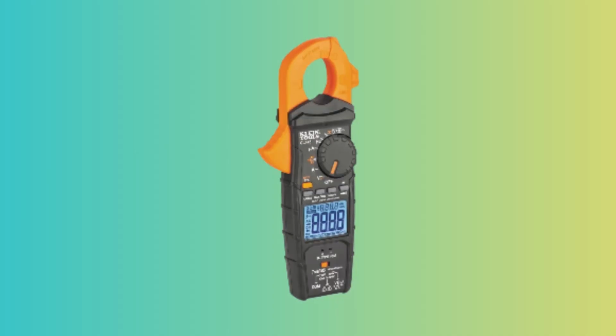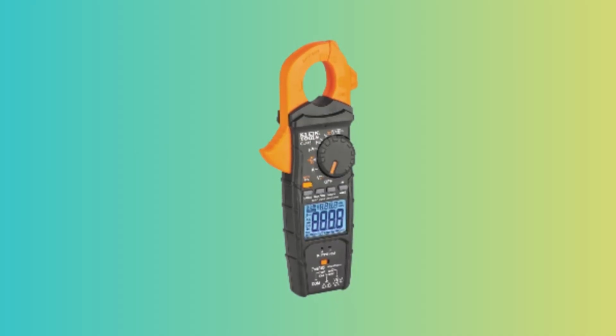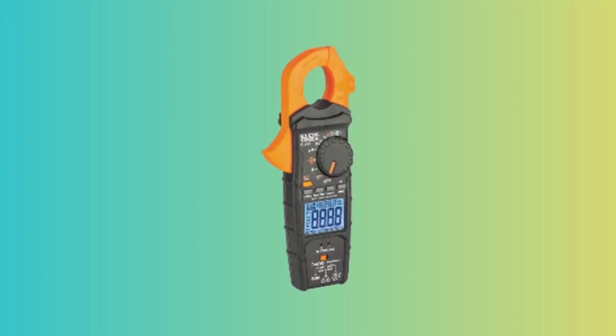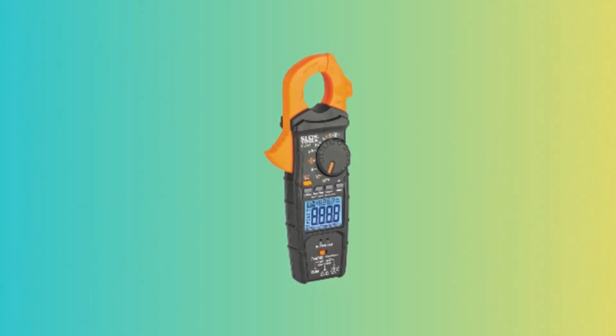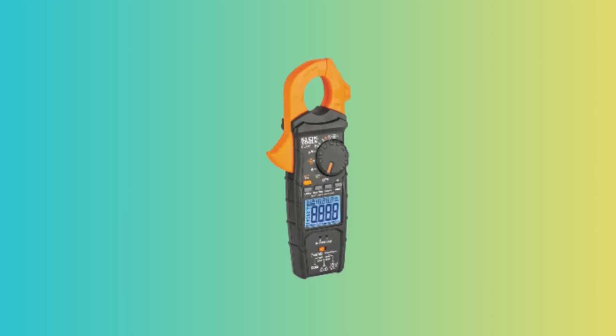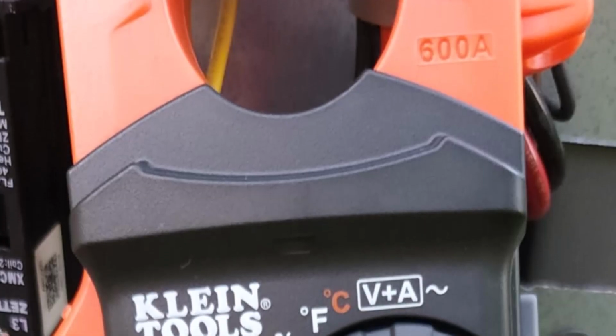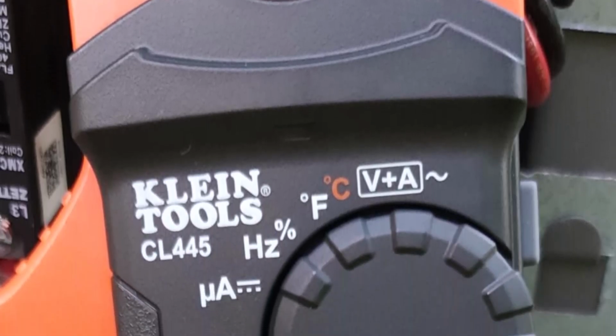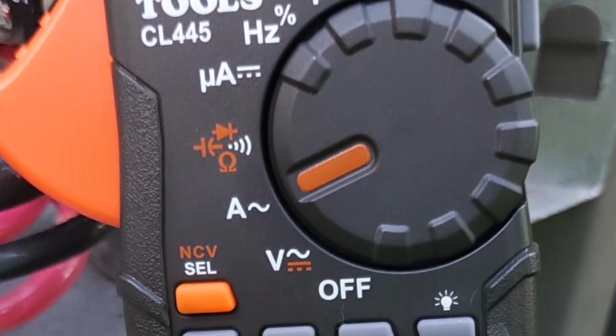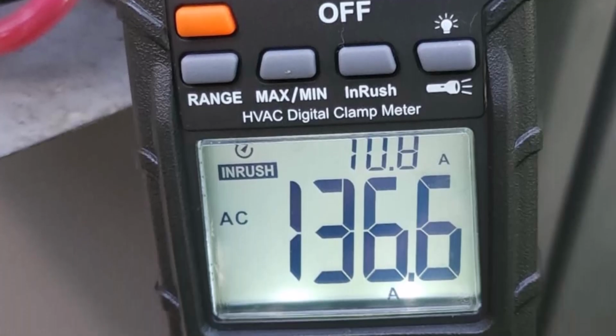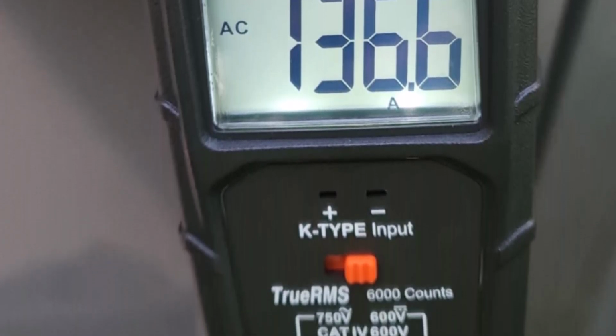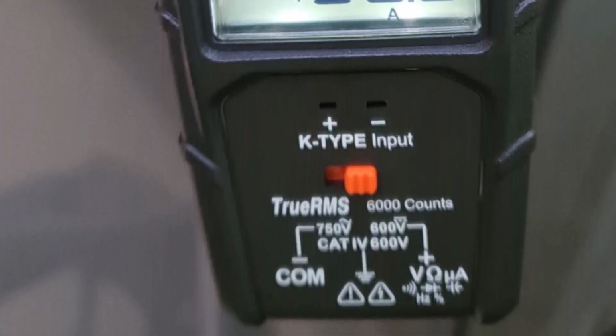Practical features like a test lead holder and optional magnetic hanger enhance usability and allow for hands-free operation in tight spaces. Added functions such as max/min, inrush, data hold, and auto power off improve versatility and help extend battery life. The non-contact voltage detection built into the clamp jaw adds safety and convenience by quickly identifying live circuits.